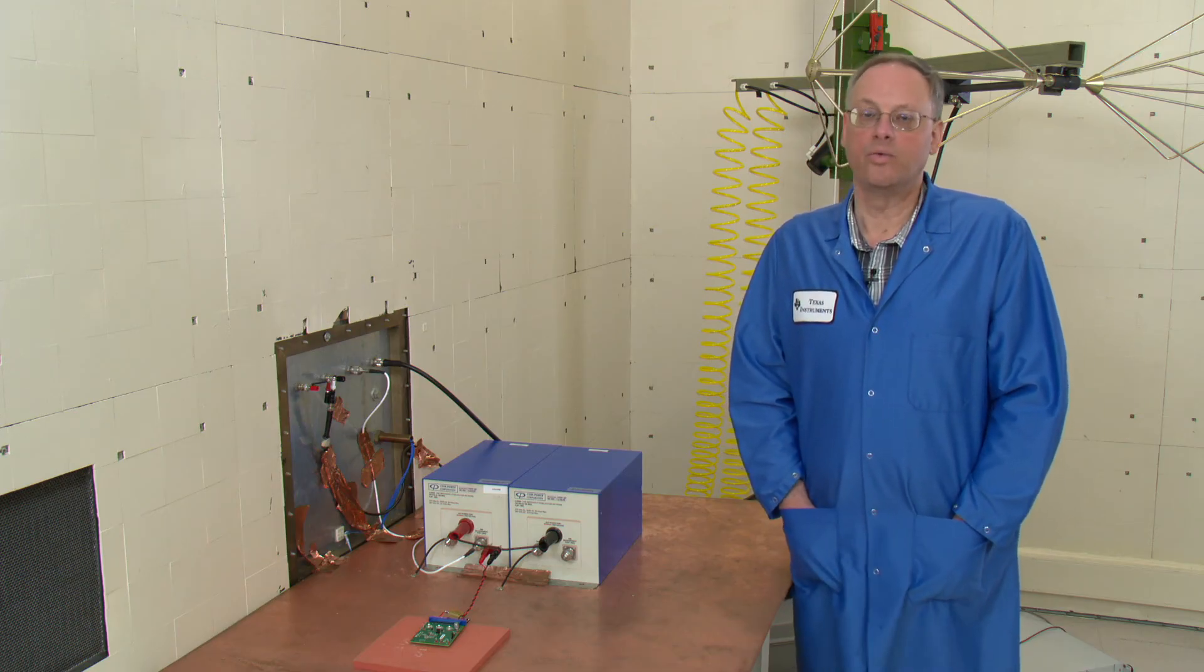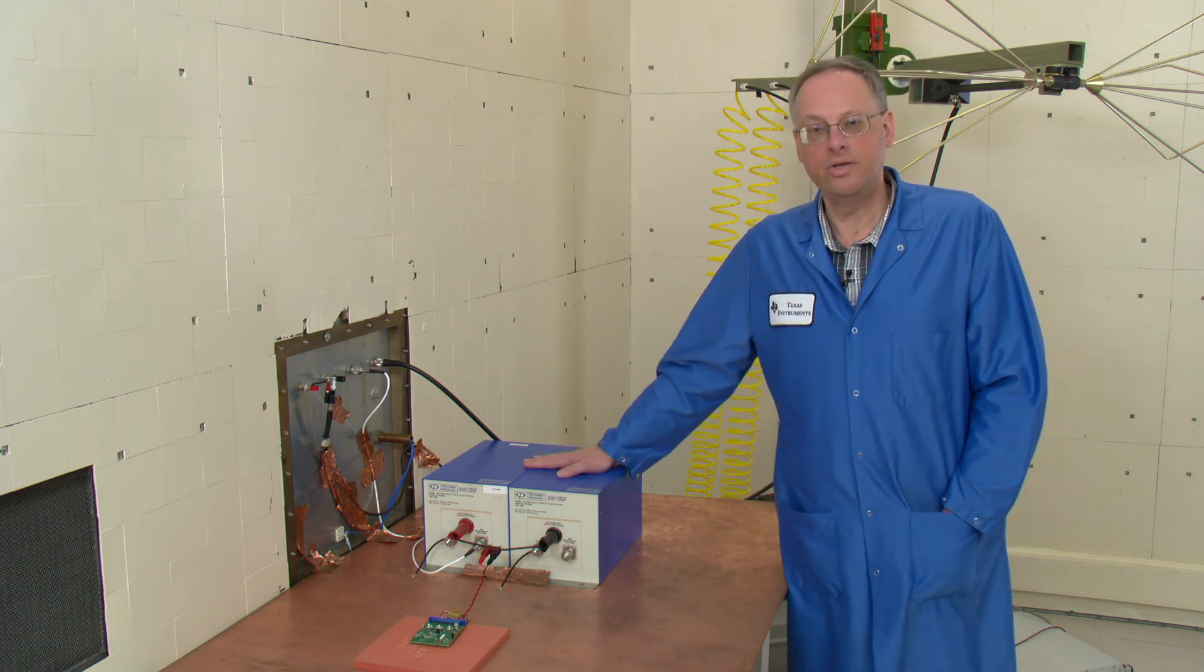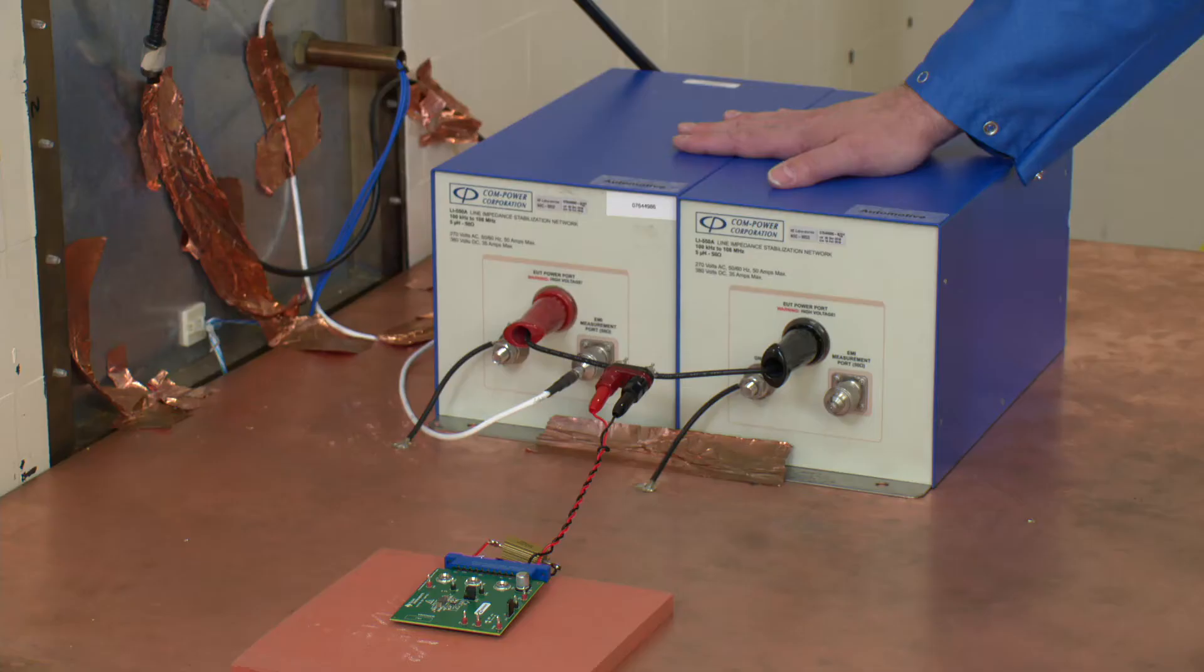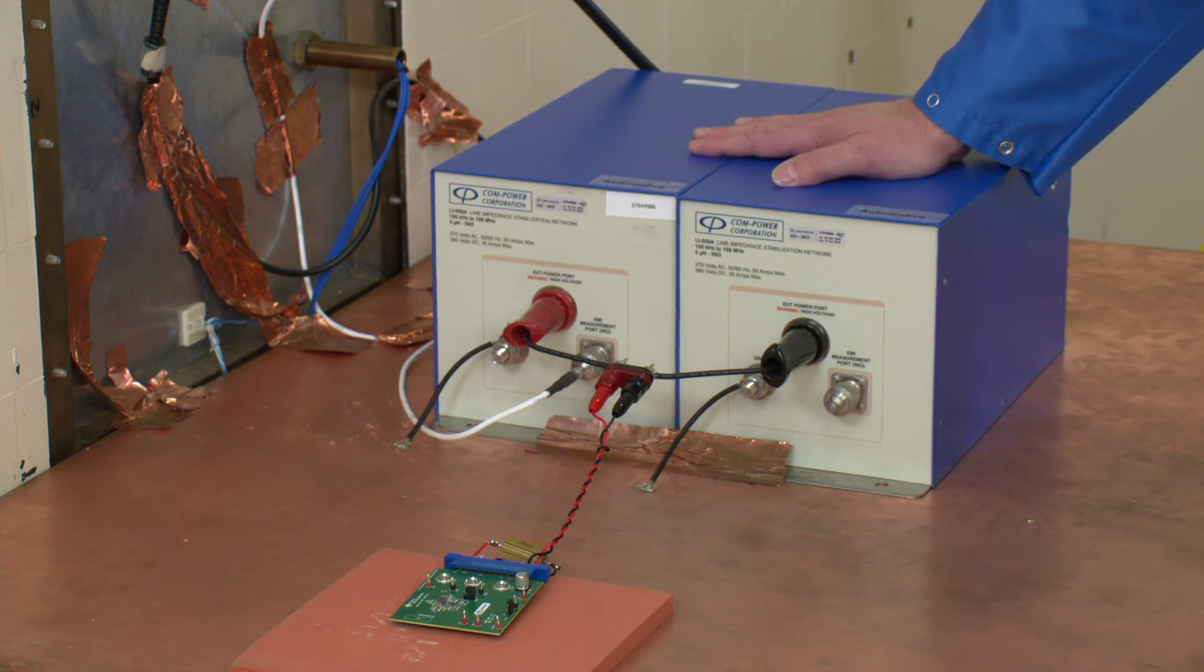So why don't we go into the chamber and take a look at the rest of the setup. Here we are in the EMI chamber with the rest of our setup. These two units comprise the LISN. The LISN separates out the noise from the DUT and sends it to the EMI receiver and bypasses the noise from the input supply. We have one in the negative input lead and one in the positive input lead.